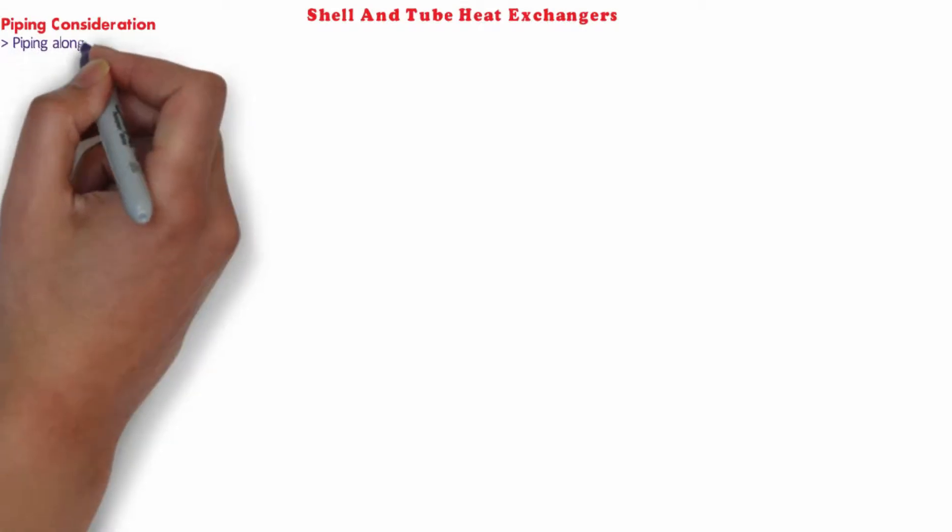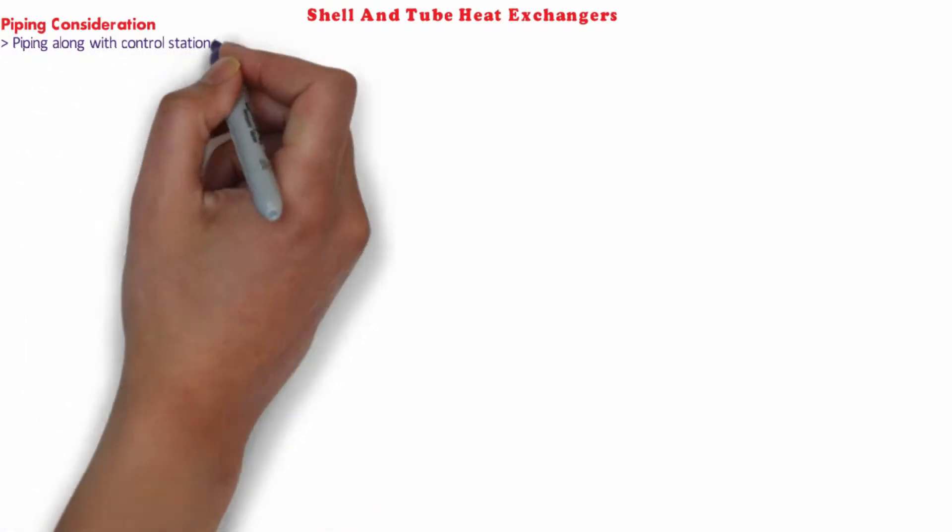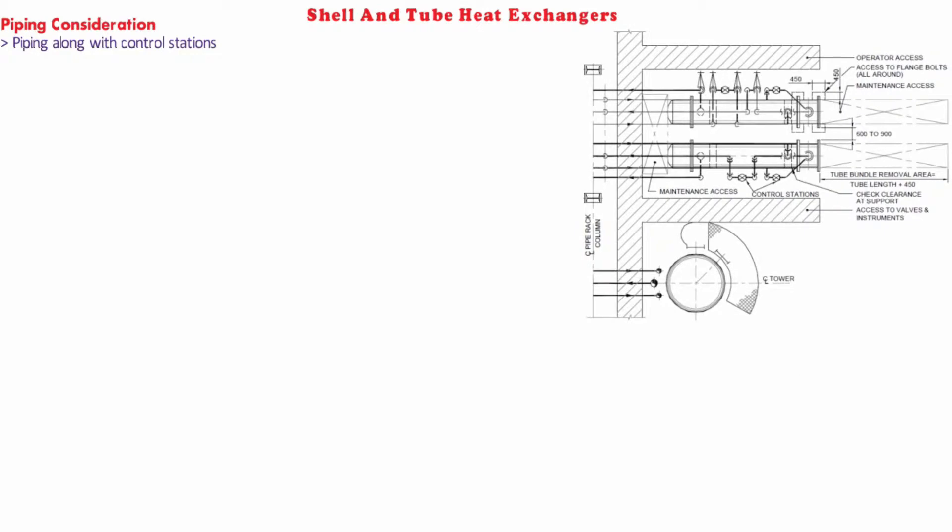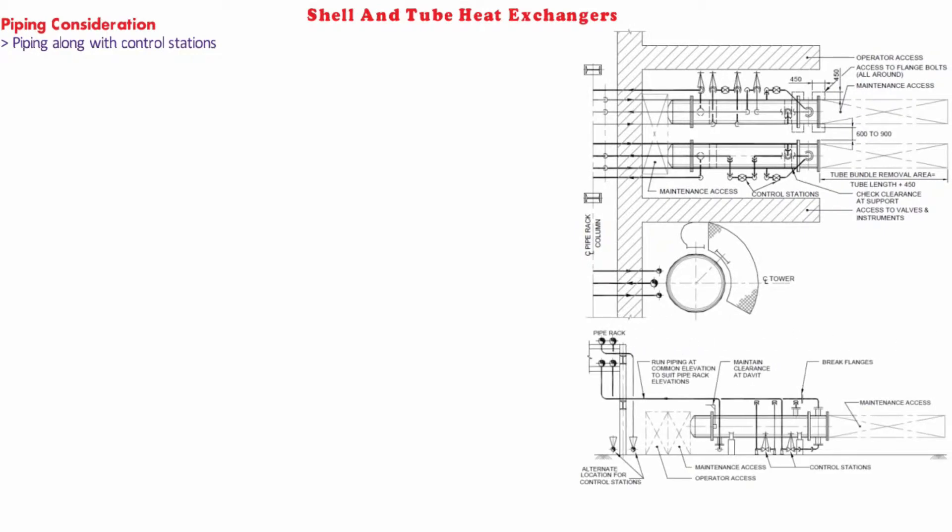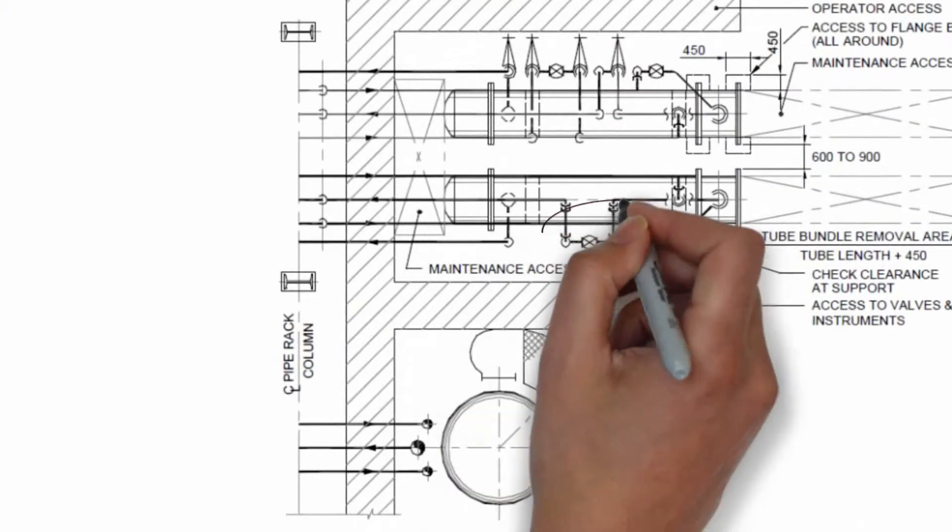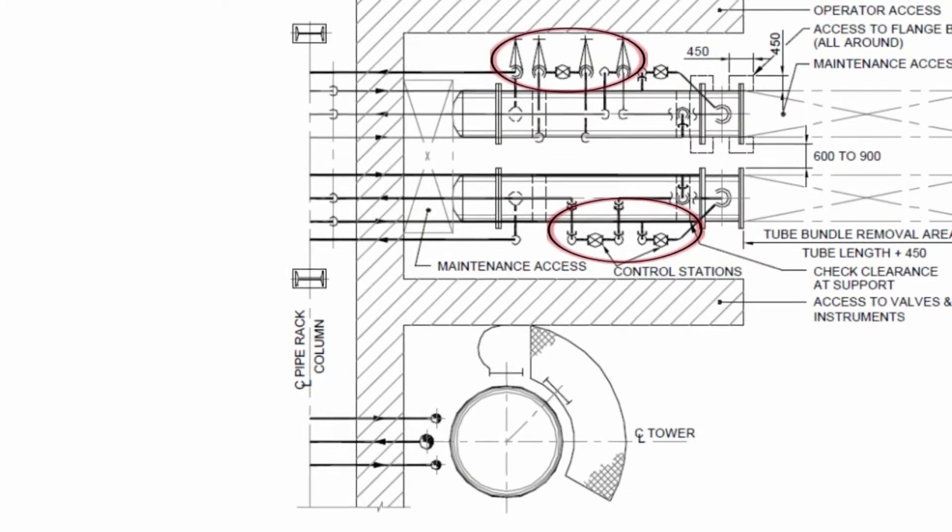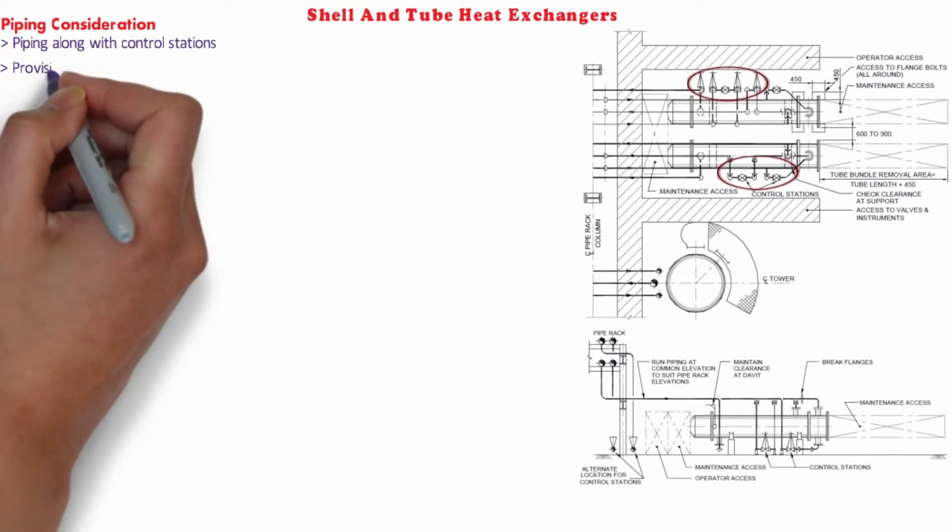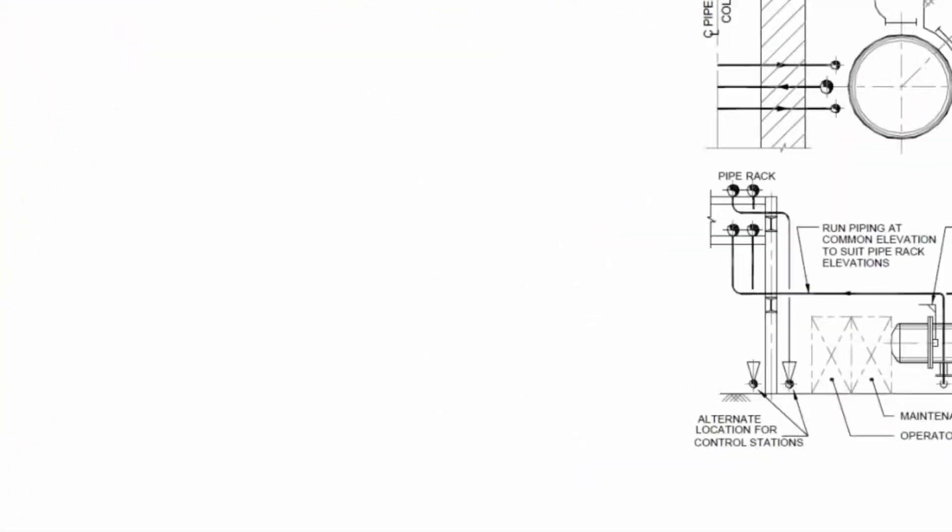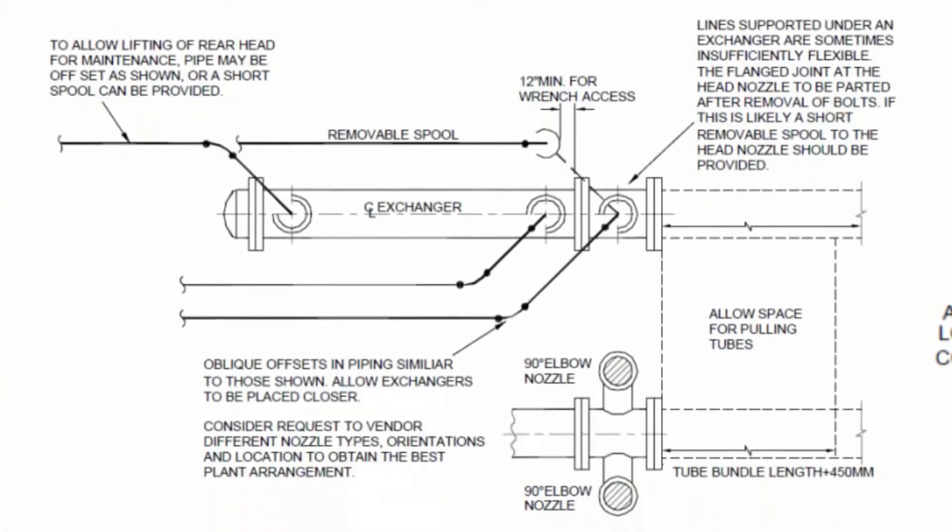The free space at the side of horizontal shell can be used for placement of control stations. The piping is elevated from grade to have a clearance of 300 mm from the grade level. Removable spools should be provided on the lines connected with the removable part of the exchangers for ease of maintenance.